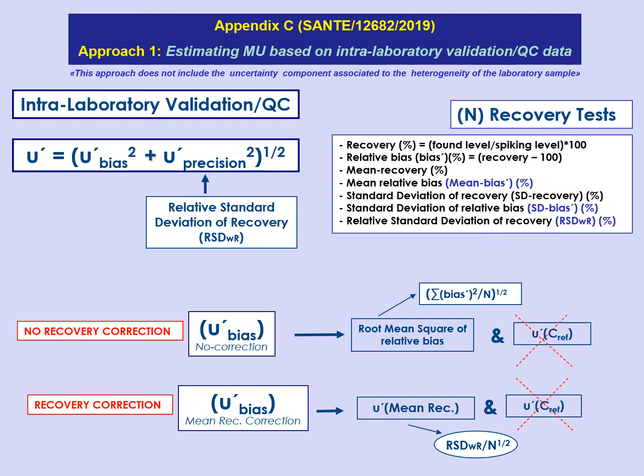When the analytical results are reported corrected with the recovery factor, that is, multiplied by 100 and divided by the mean recovery, the bias uncertainty component is actually the uncertainty of the value of the mean recovery, which is equal to the relative standard deviation of the recovery values divided by the square root of the number of recovery tests performed. In both cases, it is assumed that the uncertainty of the spiking level in the fortified samples is negligible. On the other hand, in all cases, the precision uncertainty component is assumed to be equal to the relative standard deviation of the recovery values obtained in the N recovery tests.